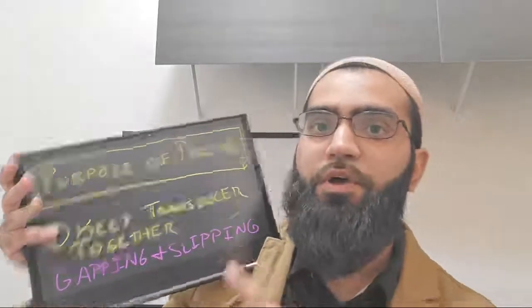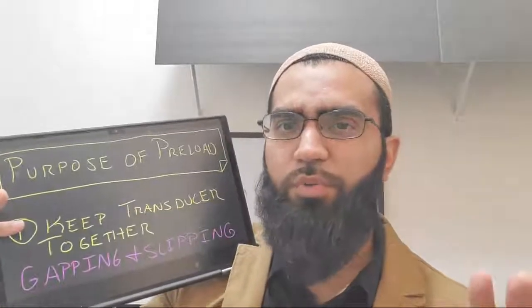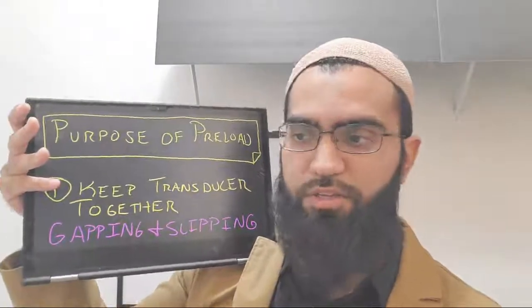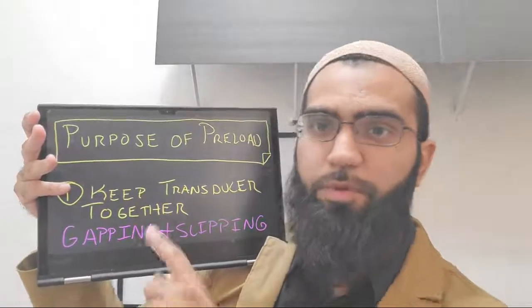The next one is slipping. If you have gapping, or a little bit of separation between the components, the crystals or the other components can slip, because although you have a bolt clamp, the threaded portion of the clamping mechanism is perhaps only on the back mass and on the horn, or it's a bolt which doesn't thread onto the back mass, but the threaded part is on the horn, for example. In that case, you may have slippage between the other components, like the crystals or other passive mass or elastic components in that train, including the back mass. So you can have slippage, which is going to really reduce the efficiency and performance of your device, and it's going to make it seem quite unusable.